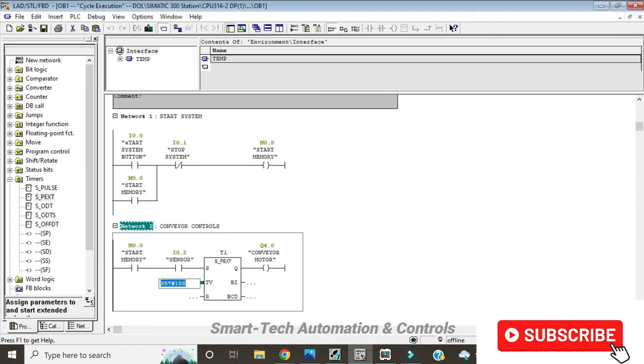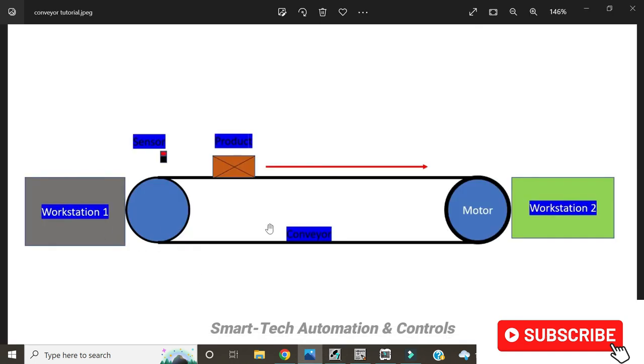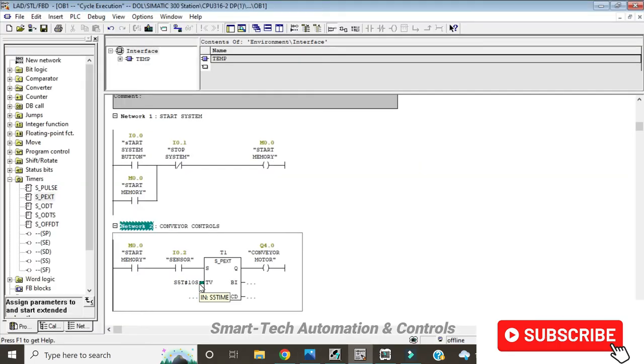Here you must first calculate the maximum amount of time the product takes to travel from workstation 1 to workstation 2. This value here must always be greater than that duration of time, because you don't want an instance where the conveyor stops before a product reaches workstation 2. For the reset signal here, this will be the signal from the stop button, and so the address will be I0.1.